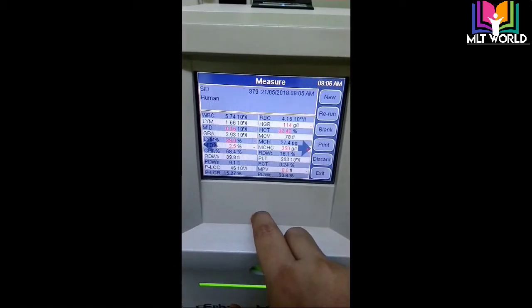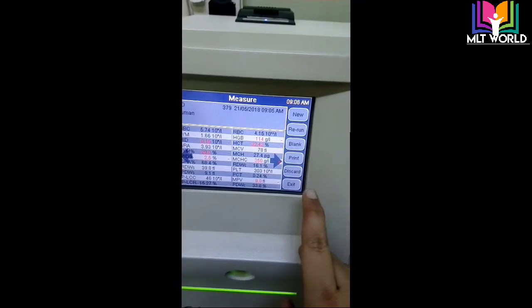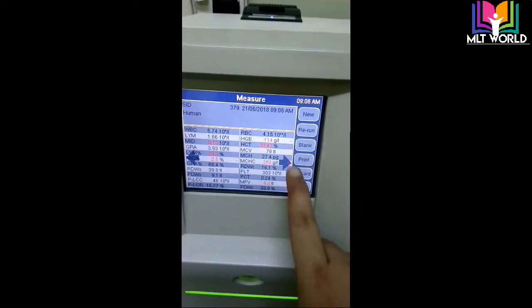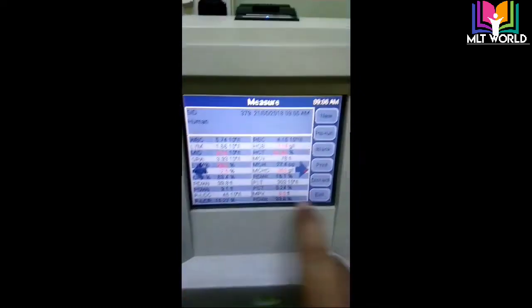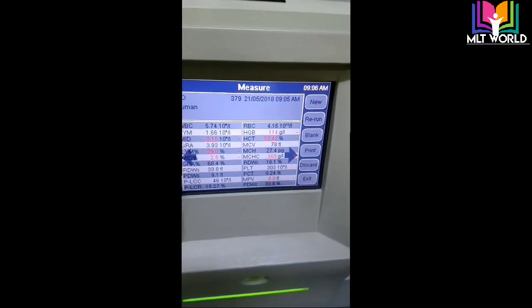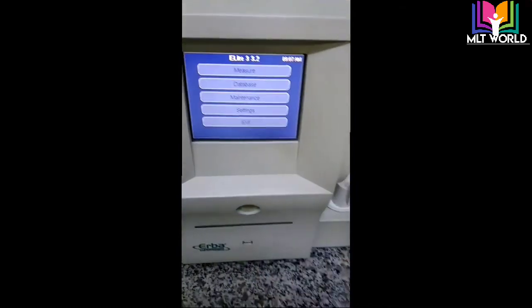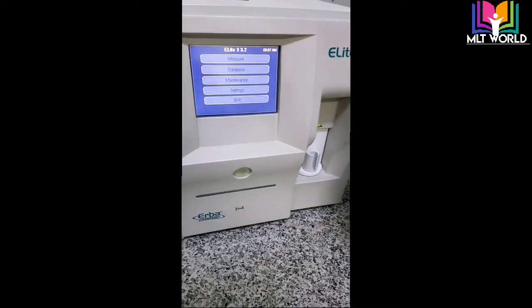If you find a significant difference between neutrophil and lymphocyte results, you can check eosinophil manually. In my next video I will show how to do a manual eosinophil count. If I want to print, I click on print. To run the next sample, I go to 'new'. To go to any other function, I click exit. If a wrong result came and I don't want to keep it, I click discard. If a clot occurred and 'C' appears — C means clot — I will first run blank, and if the issue persists I will go to maintenance and the cleaning process. Thank you so much for watching. If you like my channel, please subscribe to get updates.